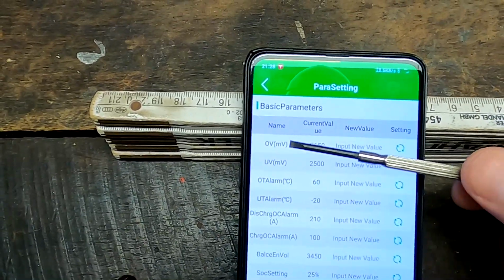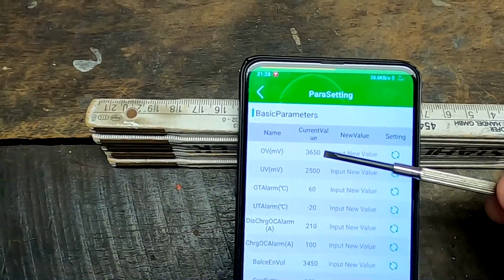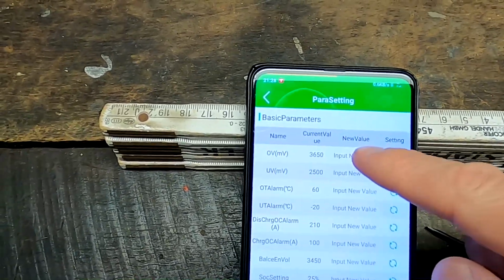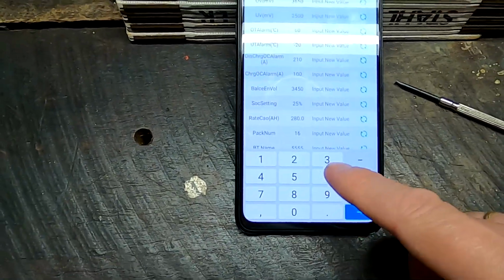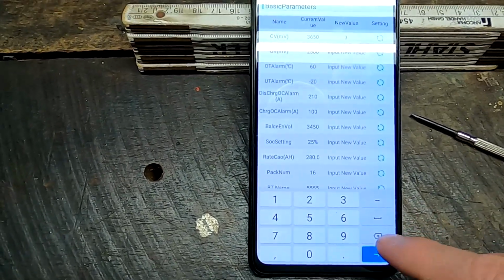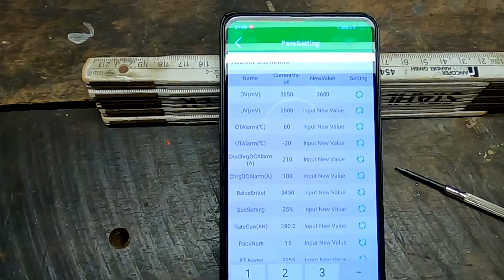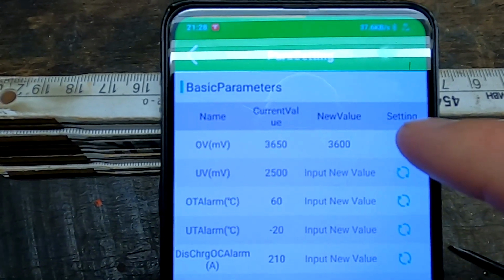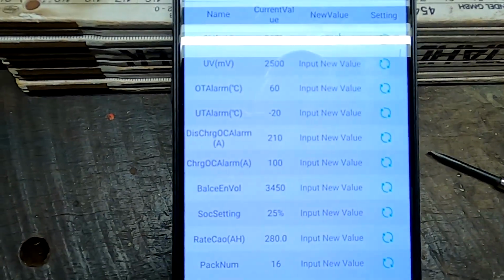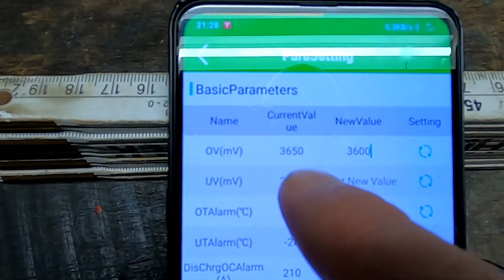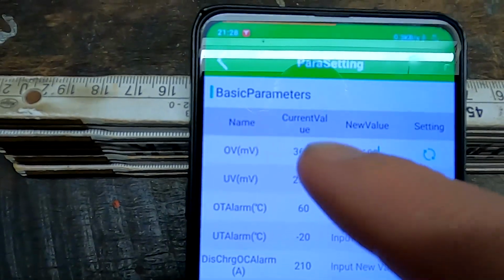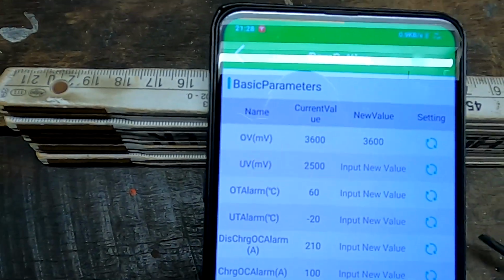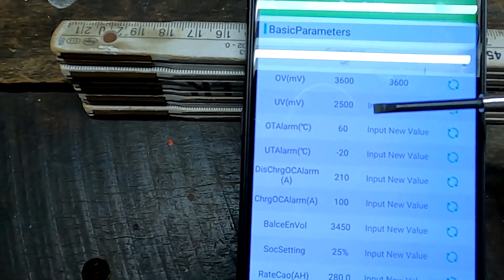Very quickly: over voltage, 3.65 volts. You can just tap in here, 3600, and then press this update button here on the side. Brings up this confirmation, and then after a few seconds it changes your parameters to whatever you set it to. The same for the under voltage, 2.5 volts.